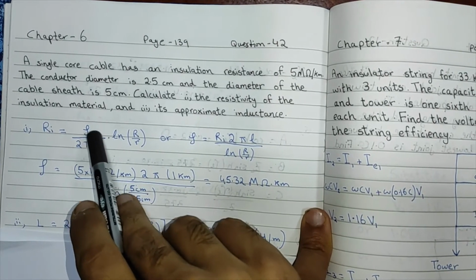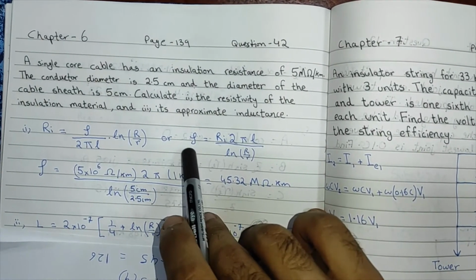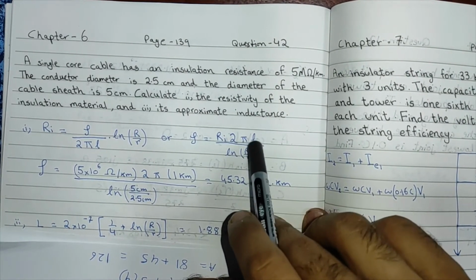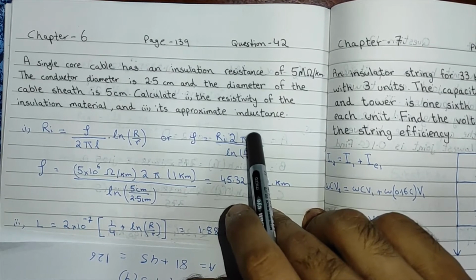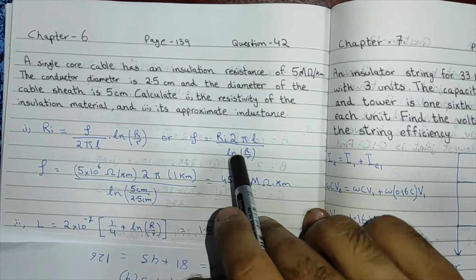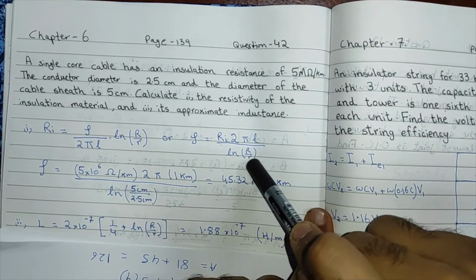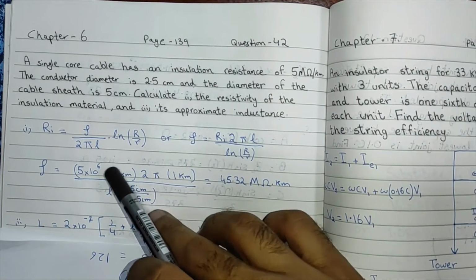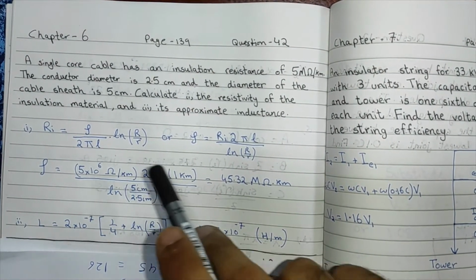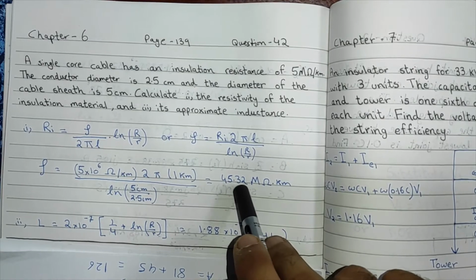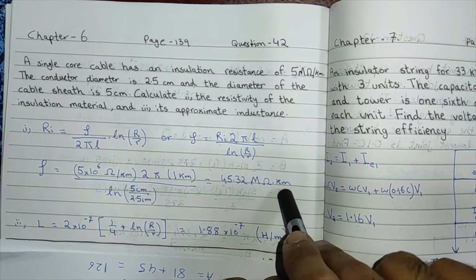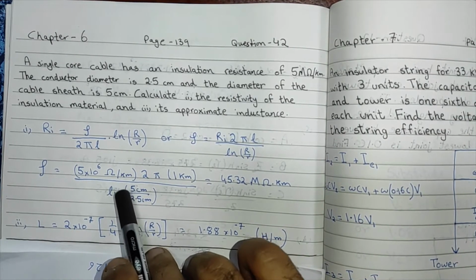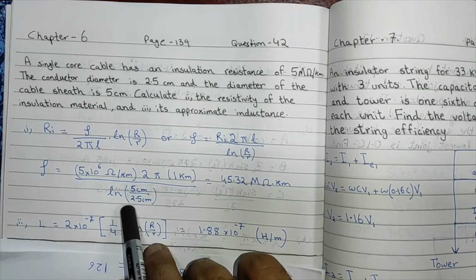So if we just rearrange this and solve it for resistivity, we can write it as resistivity equals insulation resistance times 2 pi the length of the material, divided by the natural log of the sheath radius over the conductor radius. If you just plug in the values here, you will find the resistivity to be 45.32 mega ohms times kilometer.